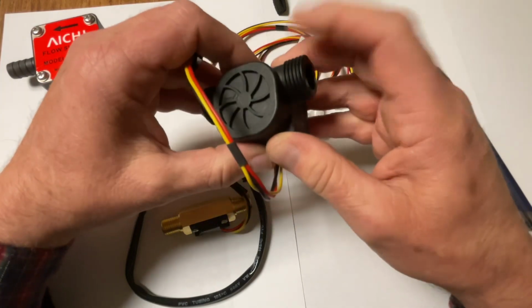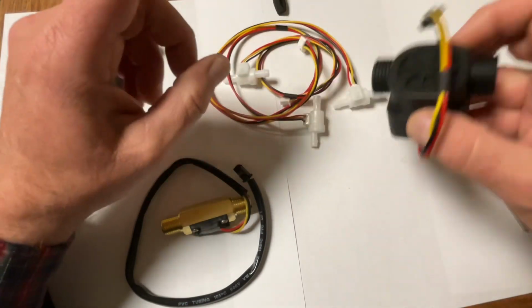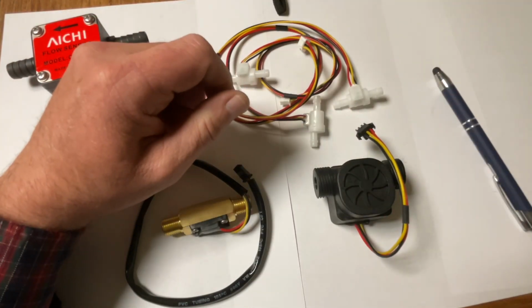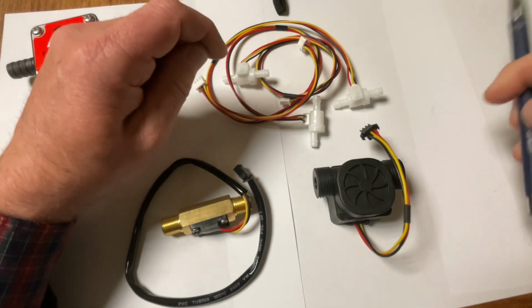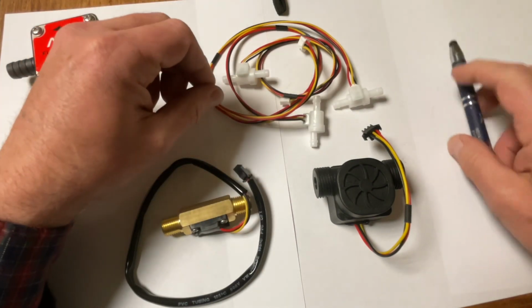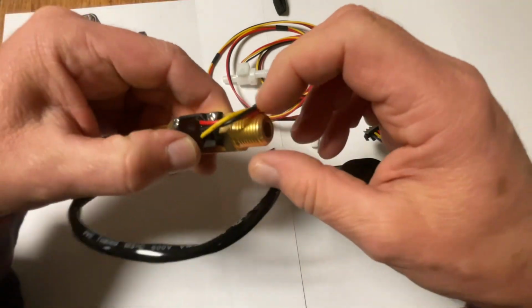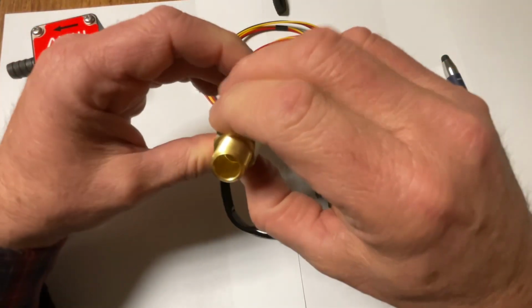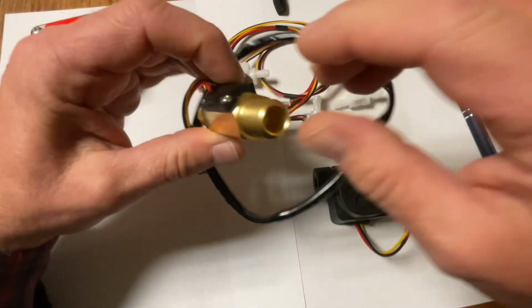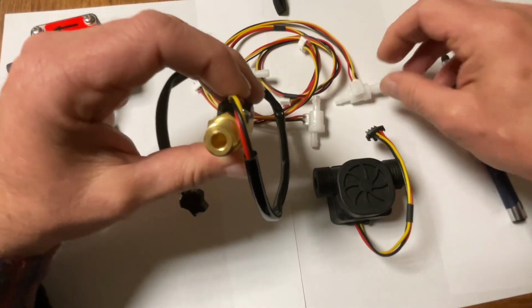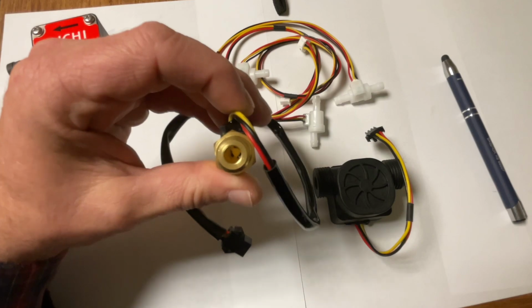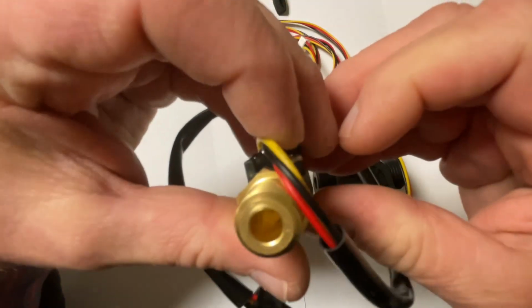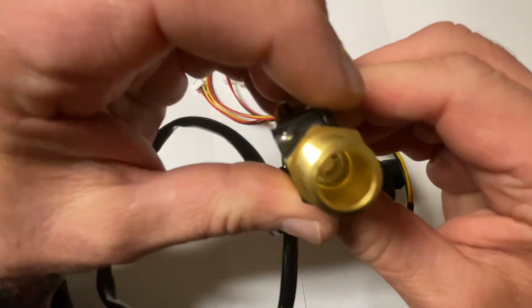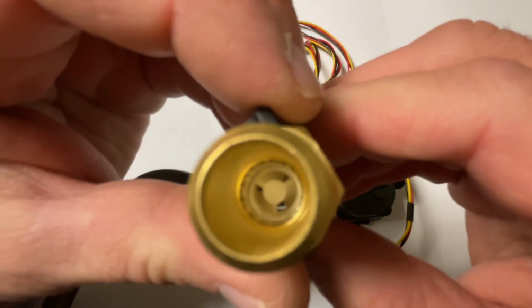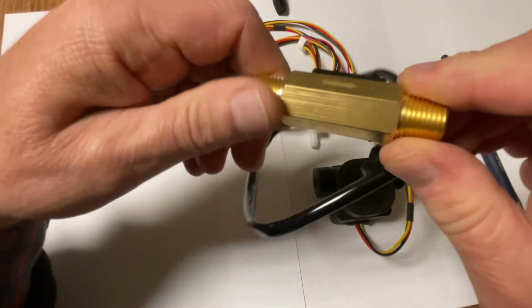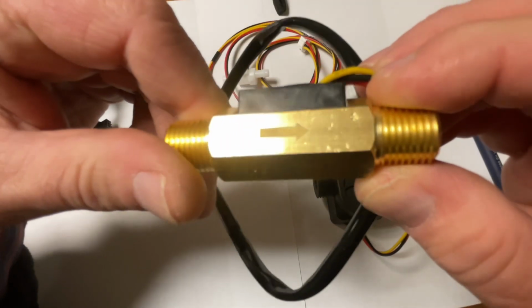And by knowing, you have to look at the data sheet. It will tell you for each on this type how much volume of fluid this actually equates to. And the problem with these here is the flow rates need to be higher. They need to be about 50 milliliters per minute at the very most, even for the small ones. They don't make anything that small to do 4 milliliters or 6 milliliters, which we actually need for the calibration. Here you can see the little turbine really well. The units, I think, are handmade. You can see the markings here from when they were put in a vise.